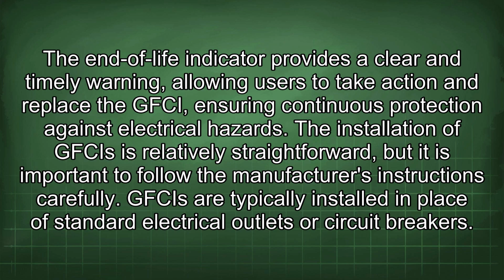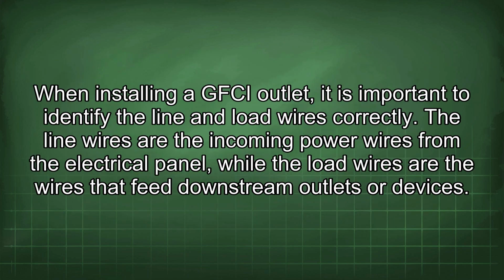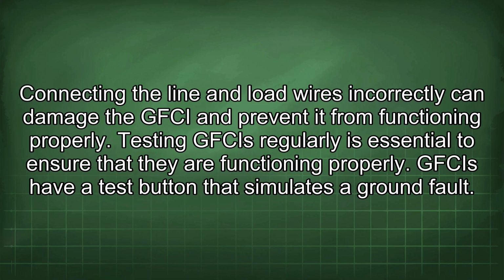The installation of GFCIs is relatively straightforward, but it is important to follow the manufacturer's instructions carefully. GFCIs are typically installed in place of standard electrical outlets or circuit breakers. When installing a GFCI outlet, it is important to identify the line and load wires correctly. The line wires are the incoming power wires from the electrical panel, while the load wires are the wires that feed downstream outlets or devices. Connecting the line and load wires incorrectly can damage the GFCI and prevent it from functioning properly.